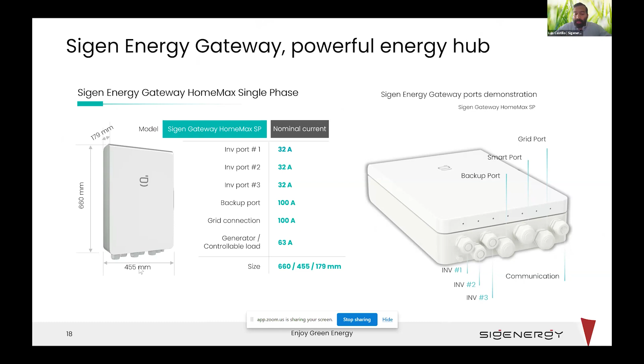We have recently made a modification to our gateway, because, as I mentioned at the beginning, we added new larger single phase inverters at 8, 10, and 12 kilowatts. So we upgraded one of the breakers of the gateway with a higher capacity. If you have one of those inverters, you should connect it to that specific port. All of this information is, of course, available on the installation manual.